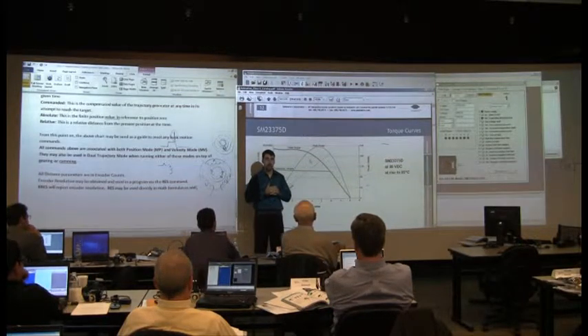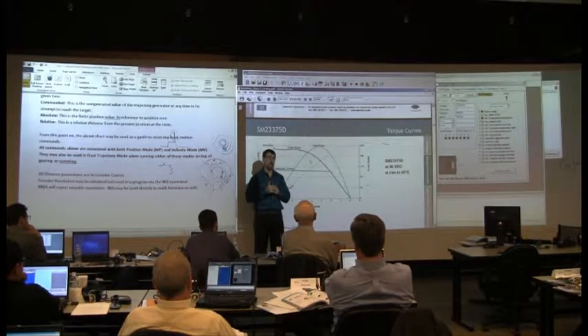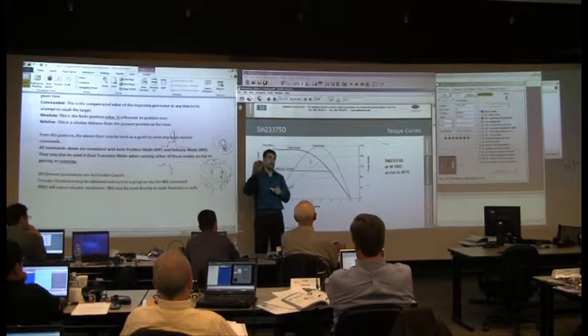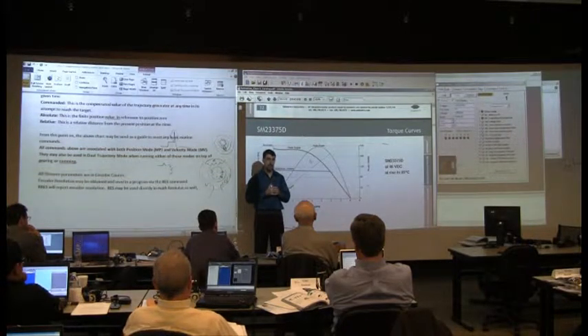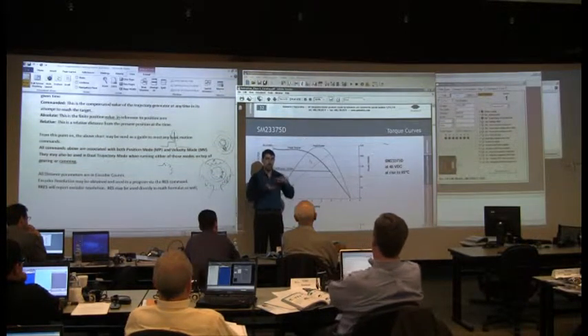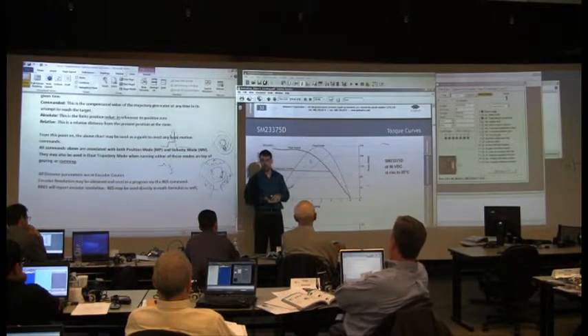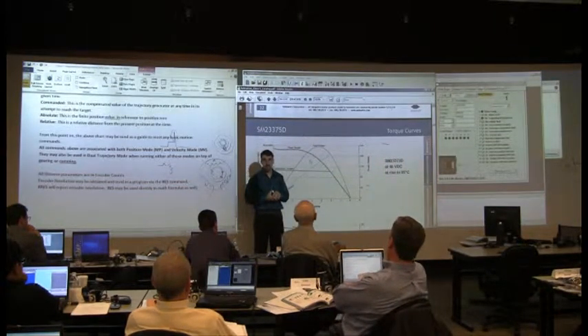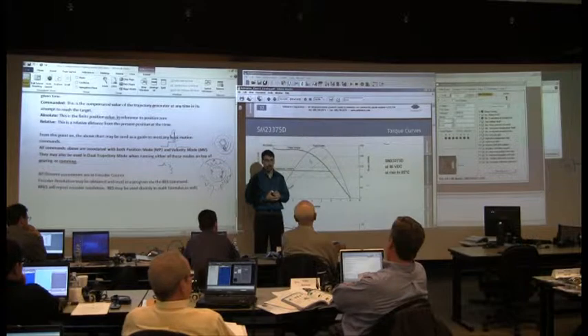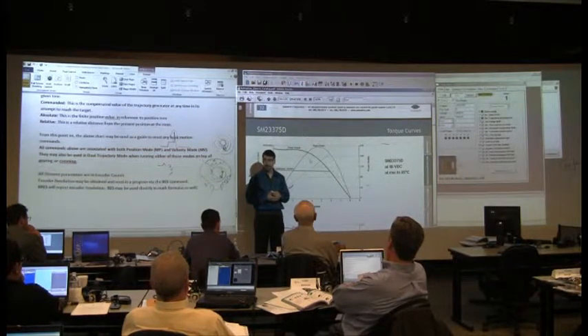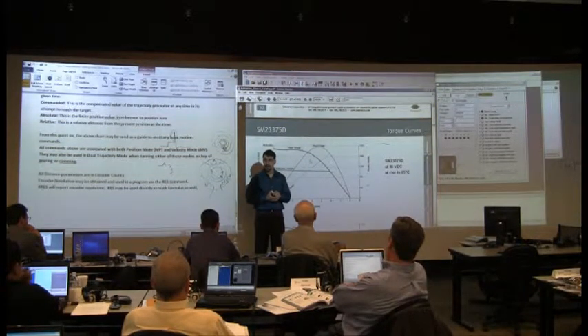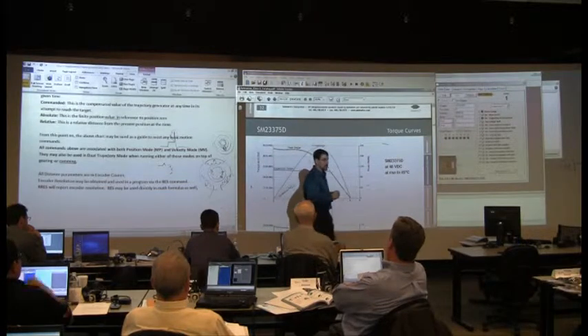But he was getting an overvoltage trip in excess of the supply voltage, and load was going down, and gravity's pulling it down. So how is he getting overvoltage? Overrunning it? Think about what happens when it goes down.